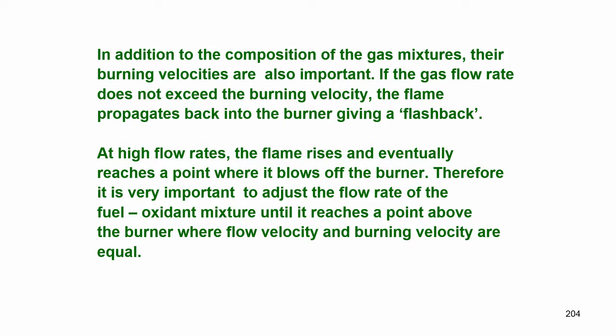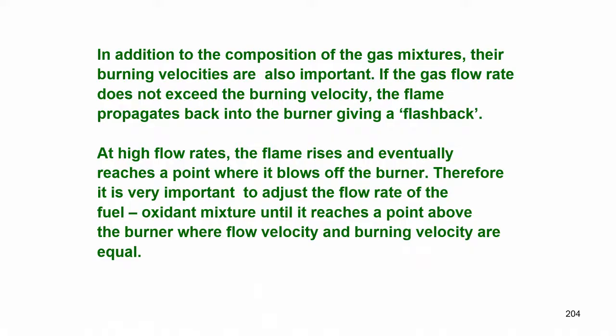So, at high flow rates, what happens? If the flow rates are high, the fuel gas is more, and eventually it reaches a point where it blows out of the burner. There are instances where the whole burner itself is blown off. Therefore, it is very important to adjust the flow rate of the fuel-oxidant mixture until it reaches a point above the burner where flow velocity and burning velocity are equal. Both should be equal.